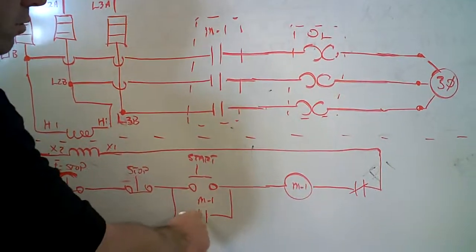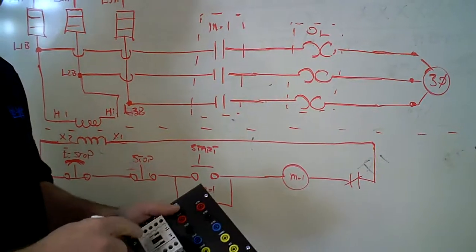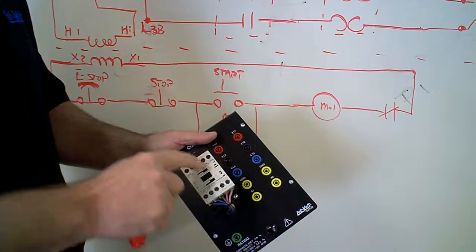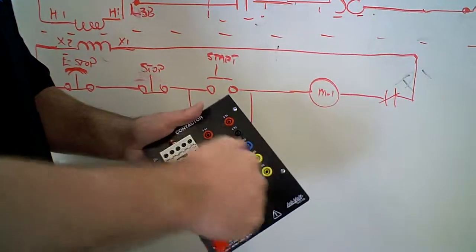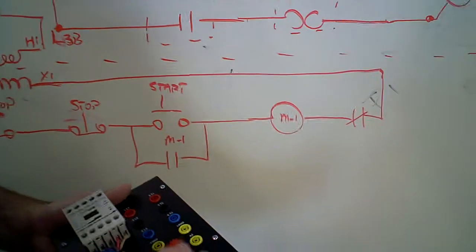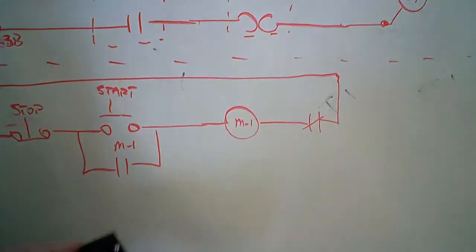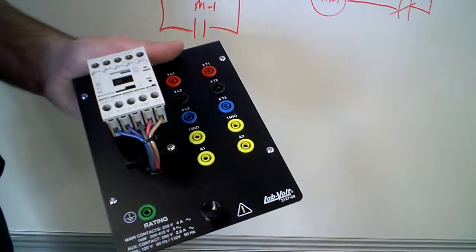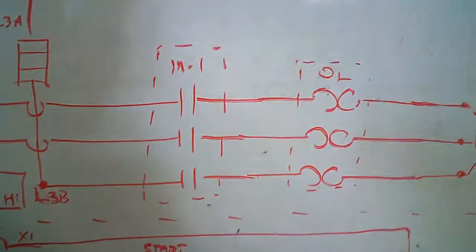These two contacts are auxiliary contacts. They are located on here too. Normally open right here. It's number 13 and 14. So 13 and 14 are those two contacts. And then your coil here, M1 coil, is A1 and A2. So those devices are all on the same physical device.